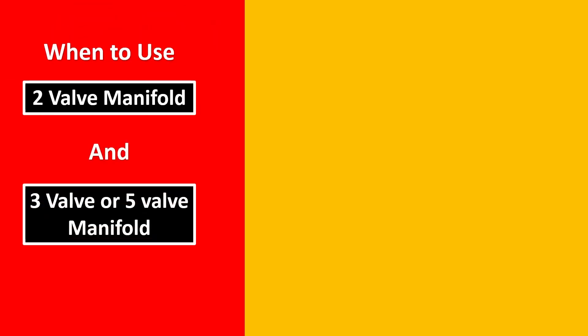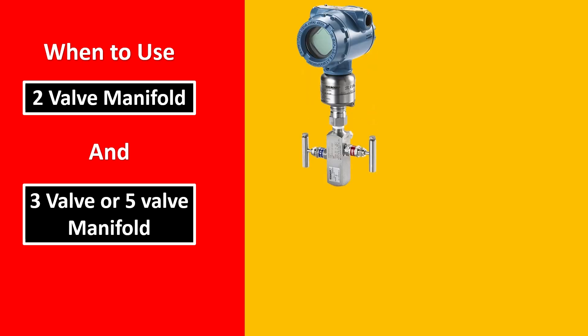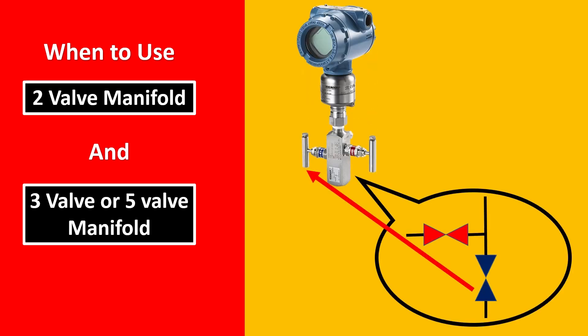Now the next thing is when to use 2 valve manifold, 3 valve manifold and 5 valve manifold. So remember that for a transmitter, 2 valve manifold is very simple. You have 2 valves to it. One is going to be your isolation valve. The other is going to be your vent and drain valve. This is how it looks in the real world. And this is the diagrammatic representation that you can draw.